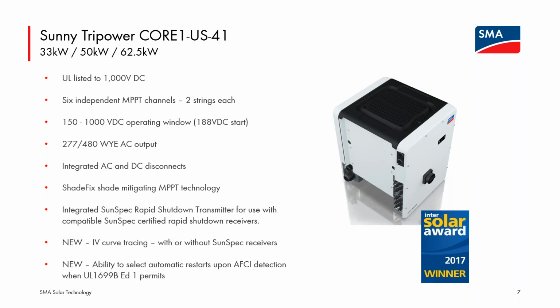I think probably not the most current, but the prior release of firmware for the CORE1 US-41 line unlocked two features in these inverters. One allows you, through the user interface of the inverter, to have the inverter perform an IV curve trace sequentially on each of its 6 inputs. So that's a very nice built-in feature that allows, I think, for good checking at a regular interval along a preventive maintenance cycle, perhaps, to do an IV curve trace on the array attached to the inverter and document that. And use that as a first step in more thorough troubleshooting if something appears incorrect in that IV curve trace. So we'll talk about that a little bit.